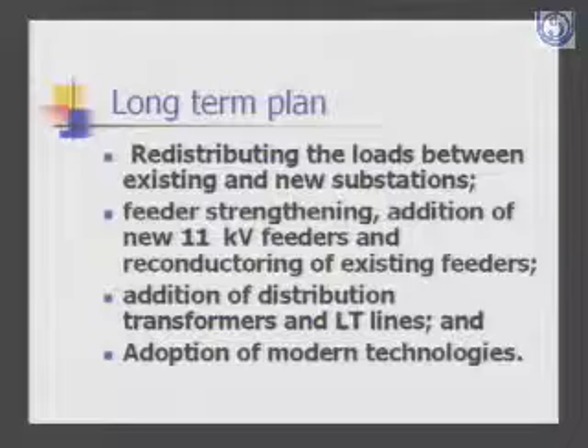For developing long-term plans, we also do system studies, called load flow studies, to check whether the long-term plan drawn up meets the statutory conditions over the 5-year period — the voltage must be within limits, the losses must be within limits. To do these studies, we use software, and various software packages are available in the market.